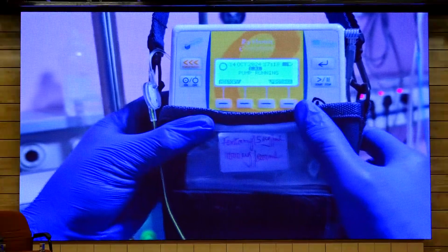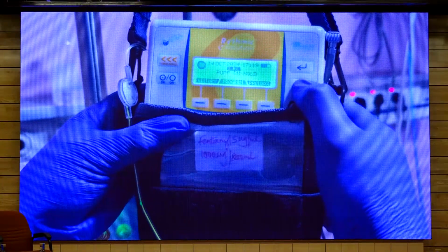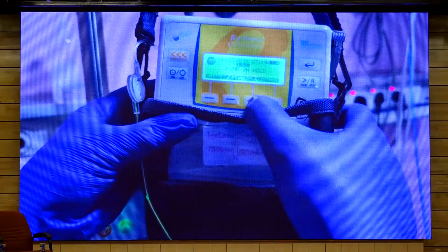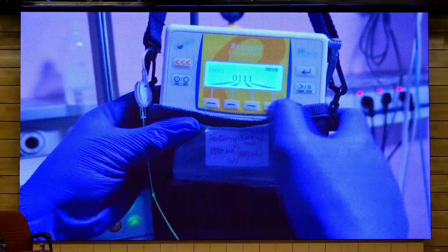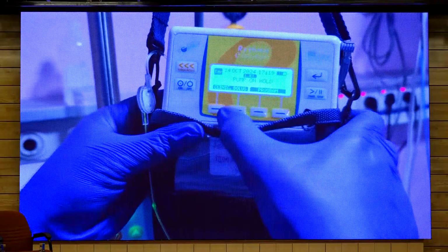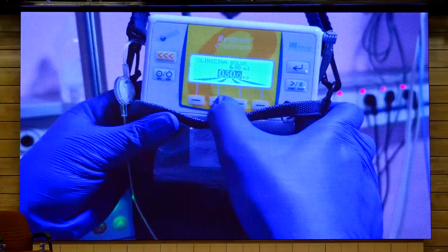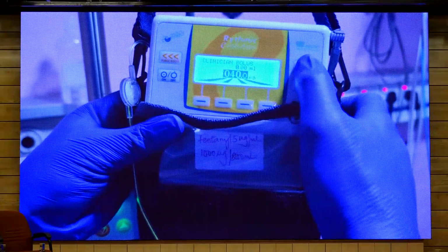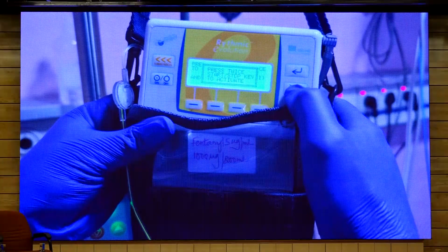To give clinician assisted bolus, stop the pump, choose program, enter safety code, press enter, select clinician bolus, select the volume to be delivered, press enter, press start key twice for the bolus dose to be administered.